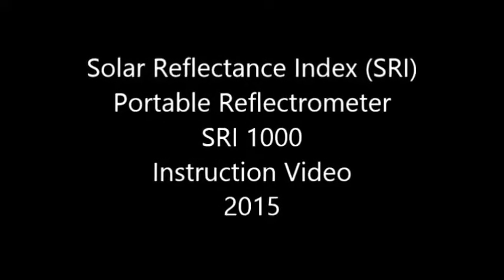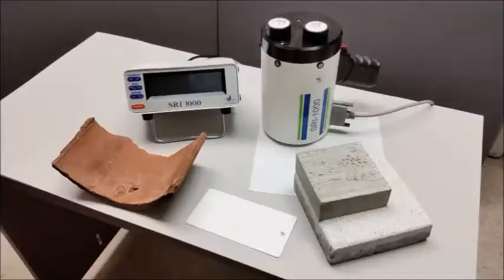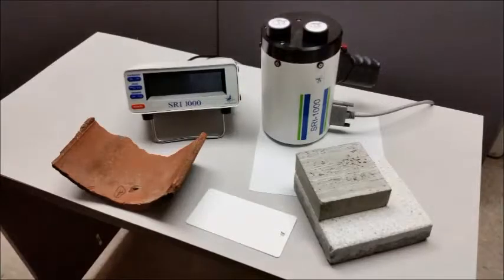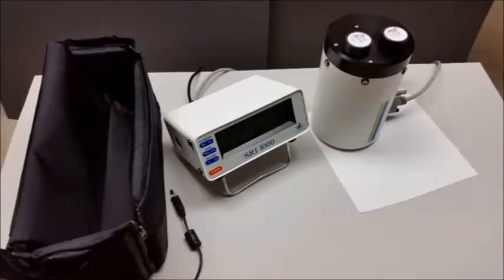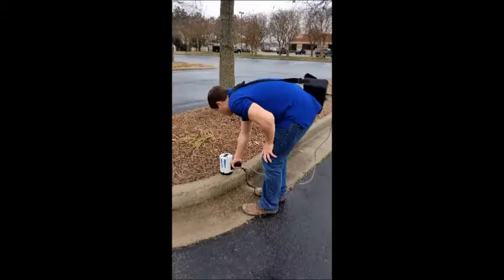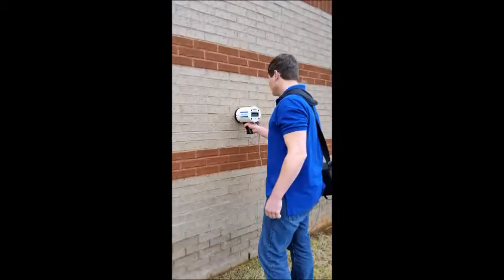The AZ Technology SRI 1000 instrument represents advanced portable instrumentation for determining thermal emittance as per ASTM E408 and solar absorptance at air mass 1.5 as per ASTM C1549 for use in calculation of the solar reflectance index using ASTM E1980. It is compact, lightweight, rugged, and ergonomically designed for ease of use in the field or in the laboratory.